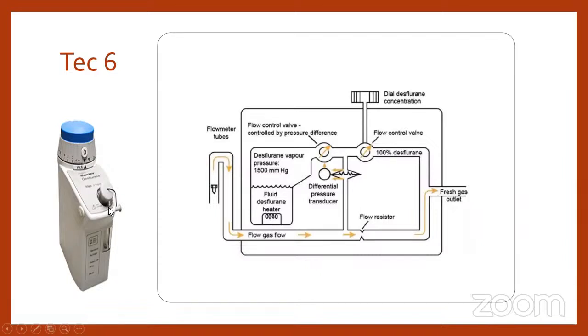Whenever we are using a desflurane vaporizer, we have to connect it to the power supply, which basically generates heat inside the chamber. Whenever the liquid gets heated, the amount of vapor will be more, and it has a series of valves to control the amount of flow. The desflurane will enter into this liquid chamber. Whenever the heater is heated, it converts the desflurane liquid into vapor, and this vapor will pass through this channel.